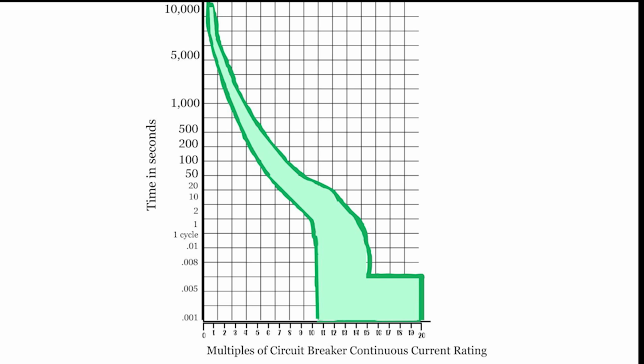So this is my representation of a time current graph. It's hand drawn. It's obviously not to scale. The numbers on the bottom, along the x-axis, represent multiples of circuit breaker continuous current rating. So if the circuit breaker is rated for 20 amps and you see down at the bottom 10, that means 200 amps. And along the y-axis is time in seconds.